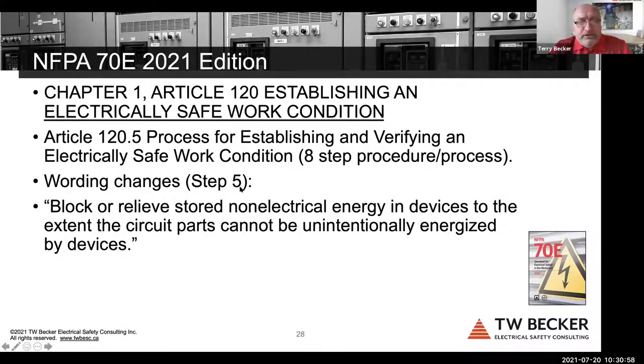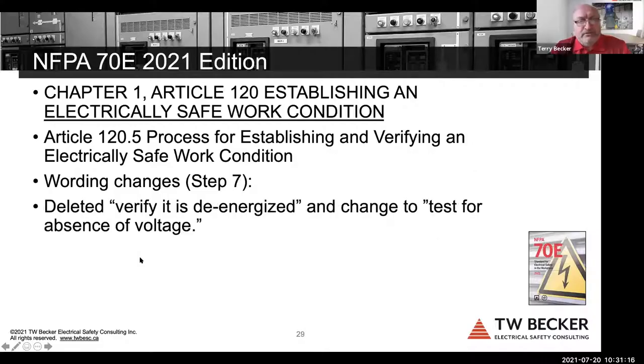So just some wording changes in the actual 8-step procedure for establishing electrically safe work condition. So some wording changes again in step 5, block or relieve stored non-electrical energy in devices to the extent the circuit parts cannot be unintentionally energized by those devices. So subtle wording changes, same overall context for establishing electrically safe work condition. Some wording changes here, verifying the energization to test for absence of voltage, the correct sort of technical words.